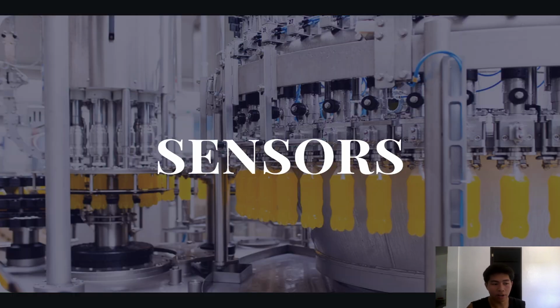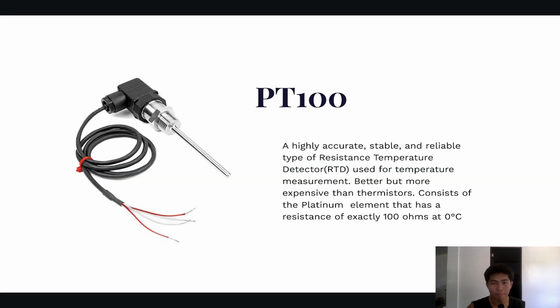Proceeding on, what are the sensors used? Firstly, for the temperature, it is the PT100. The PT100 is a resistance temperature detector, a highly accurate, stable, and reliable type of RTD. It is much better but more expensive than a thermistor. The PT stands for platinum, a material that has a resistance of exactly 100 ohms at 0 degrees Celsius and a ratio of 0.385 ohms per degree Celsius.